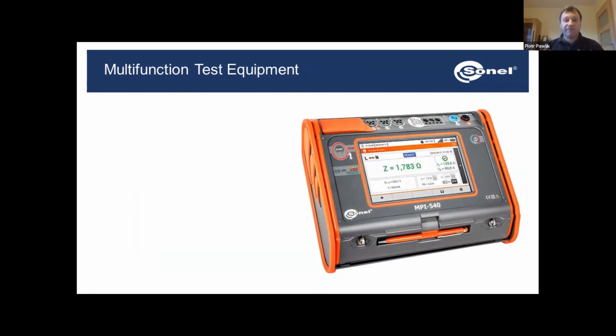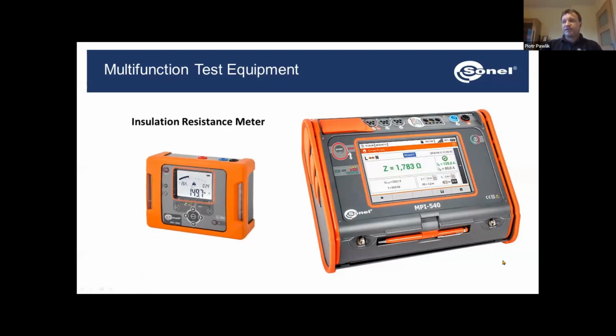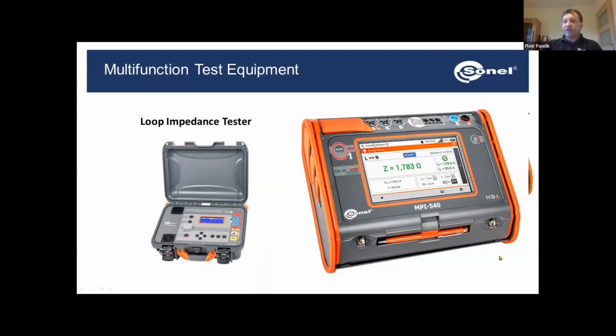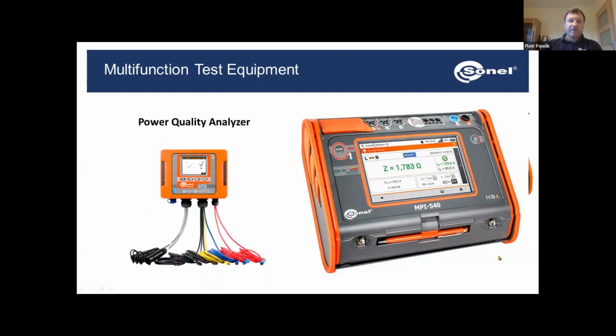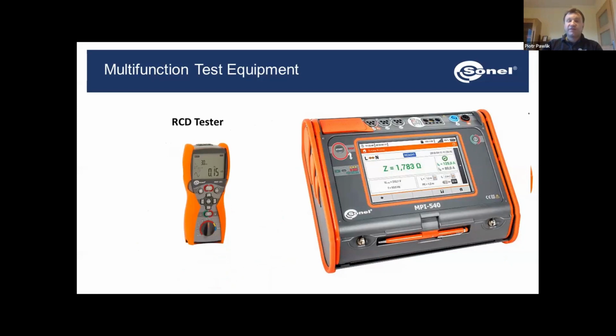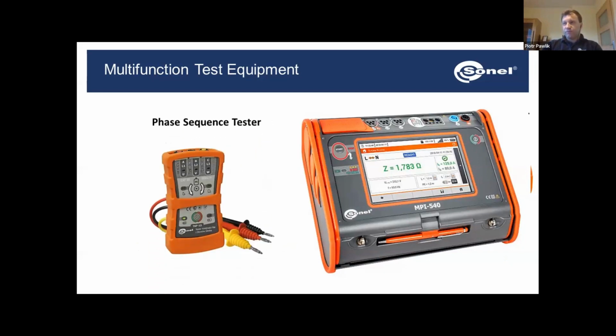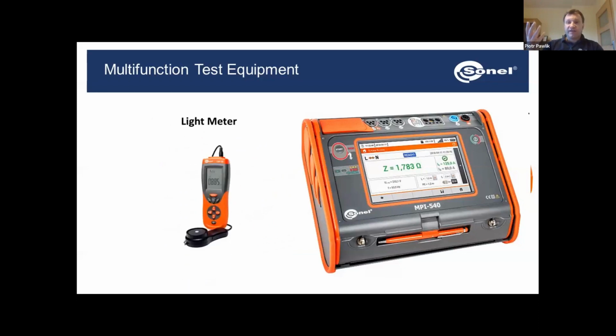Now the time has moved on and we have newer meters. For you, I would recommend our multifunction meters, because it's a single tool that allows you to measure whole electrical installations in buildings. It could be industrial buildings, commercial buildings, office facilities, as well as residential buildings. So this meter allows us to check insulation resistance, earth resistance, and to perform fault loop impedance tests. It also has a built-in three-phase power quality analyzer of class S. We can check parameters of the RCDs, the rotation of the phases, and the light intensity. So that many functions in just this one device.